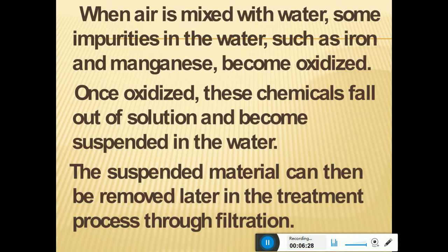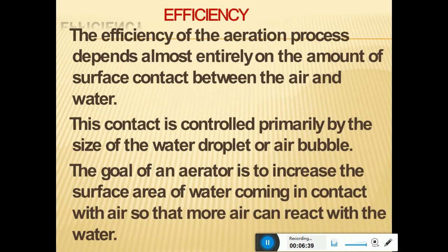So this oxidized matter can be removed in the later stages of the treatment, and this is the very basic step in the treatment of water. So what is the efficiency of this aeration process? The entire efficiency will be greatly dependent on the surface contact between the water and the air. This contact is controlled primarily by the size of the water droplet or the air bubble.